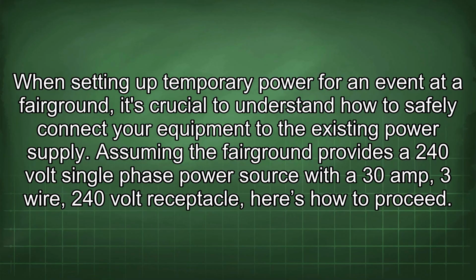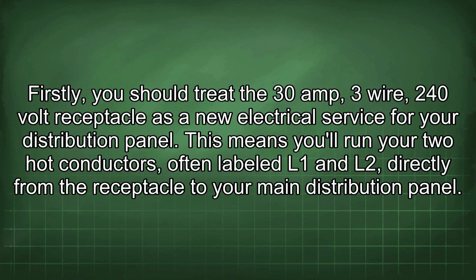When setting up temporary power for an event at the fairground, it's crucial to understand how to safely connect your equipment to the existing power supply. Assuming the fairground provides a 240-volt single-phase power source with a 30-amp 3-wire 240-volt receptacle, here's how to proceed. Firstly, you should treat the 30-amp 3-wire 240-volt receptacle as a new electrical service for your distribution panel.